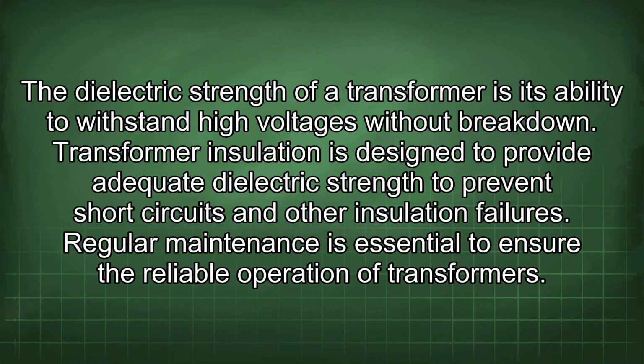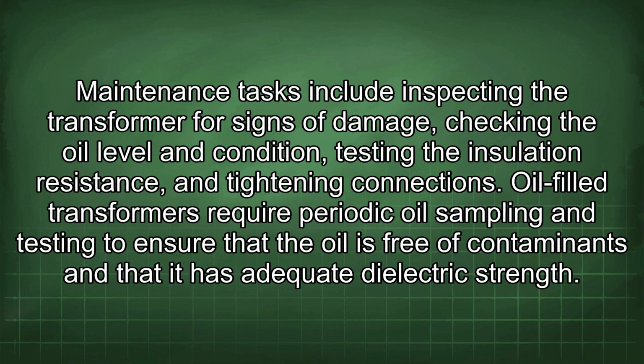The dielectric strength of a transformer is its ability to withstand high voltages without breakdown. Transformer insulation is designed to provide adequate dielectric strength to prevent short circuits and other insulation failures. Regular maintenance is essential to ensure the reliable operation of transformers. Maintenance tasks include inspecting the transformer for signs of damage, checking the oil level and condition, testing the insulation resistance, and tightening connections. Oil-filled transformers require periodic oil sampling and testing to ensure that the oil is free of contaminants and that it has adequate dielectric strength.